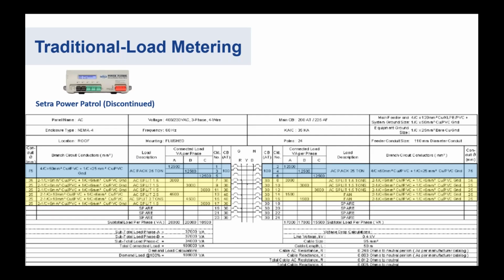We'll take a minute to talk a little bit about traditional versus multi-load metering. With traditional load metering, and we used to do this a lot with our Setra Power Patrol, which is discontinued, below, a customer sent in a requirement and we broke out the diagram. You can see in the blue our 2 3-phase loads, and then in the yellow squares, those are all individual loads that the customer wanted to measure for single-phase loads.